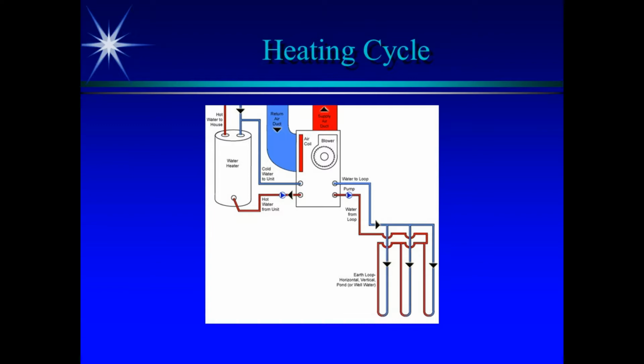We take the cold out of it, actually, and we bring the heat back in. So by having cold refrigerant exposed to that 48 to 50 degree water, the heat moves from that water, or from the ground, into that refrigerant, right? Because the refrigerant's colder, the water's warmer, heat moves to where there is no heat. So now we've grabbed the heat, it's been absorbed into that refrigerant, we move that away, and then we compress it. And when we compress it, it gets really hot, maybe 150 degrees.